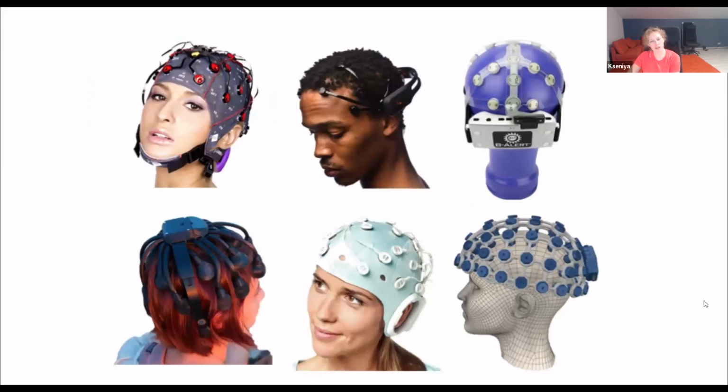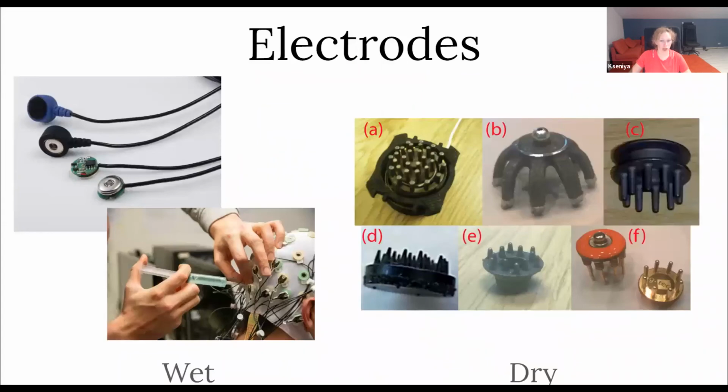Now, neurointerfaces are widely used. The main principle here is also EEG. Neurointerfaces are more transportable, sometimes with fewer electrodes and often with dry electrodes. There are two types of electrodes. There are ordinary wet electrodes, like here on the left. They use a conductive gel. And dry electrodes, here on the right, contain flexible legs made of conductive plastic. And in the next class, we will have neurointerfaces with dry electrodes.